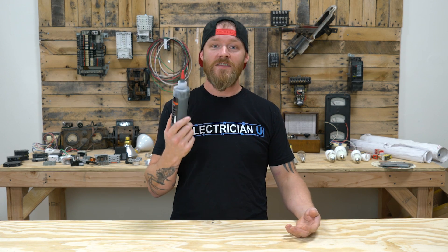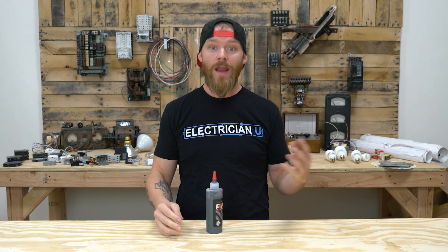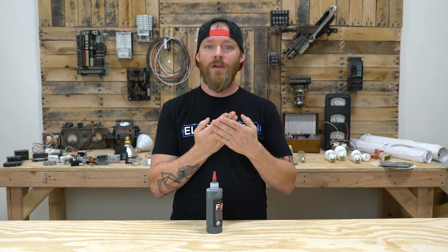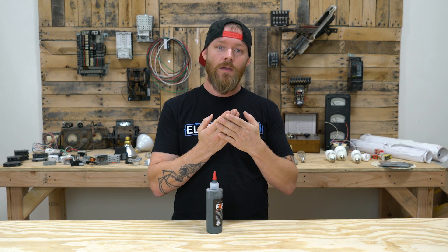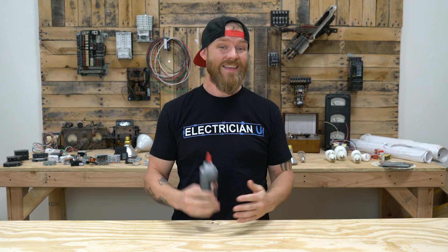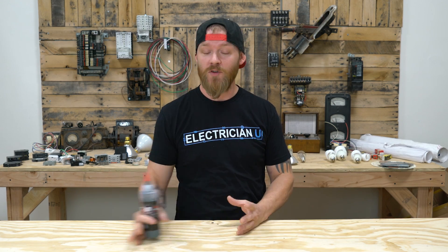I see people putting this stuff on service conductors and anything aluminum — they're just scared. Aluminum, aluminum, aluminum — you've got to put this stuff on. But the cool thing about it is the AA-8000 series aluminum, even when you mix it with copper, still does not cause the same galvanic action. It doesn't corrode one another like it used to. We've been using that same alloy since the 80s, and all these electricians, home inspectors, and homeowners are so freaked out by this whole aluminum phenomenon.